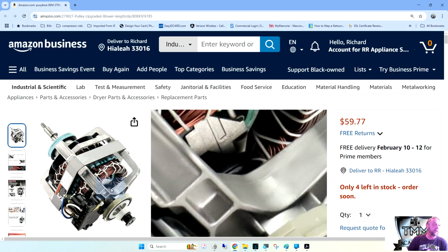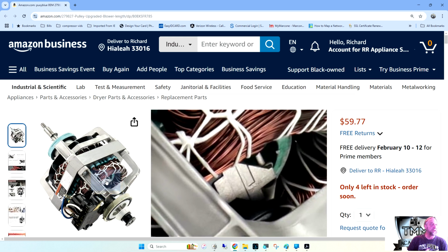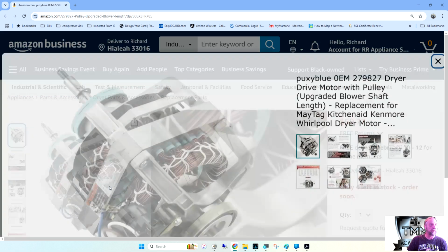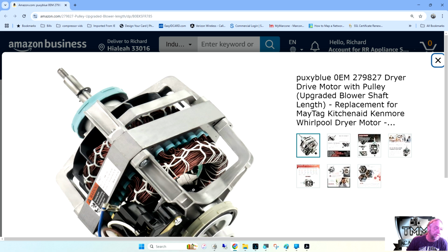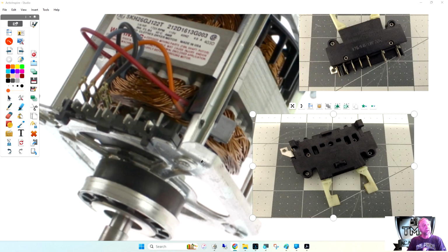If you zoom in underneath that metal piece, like right here, okay, here we go. There's a little black collar right there, and it goes all the way around the shaft of the motor, and you push it down, and that's how you activate the centrifugal switch. By pushing that collar inside the motor, you're moving these two levers and you're causing the switch inside here to either open or close.